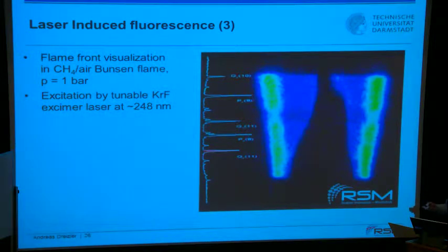They very often have, because of an unstable resonator, lower intensity at the center of their light beam. And you need to correct for the laser intensity. Without that correction, you would not be able to deduce any quantitative numbers.